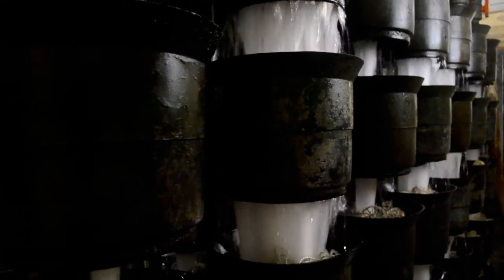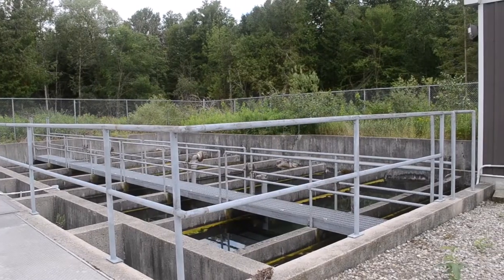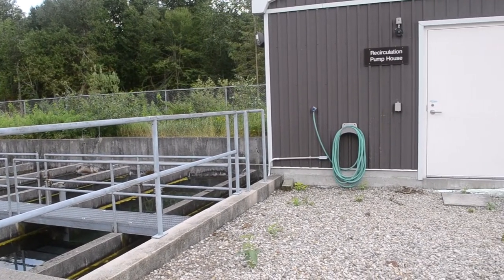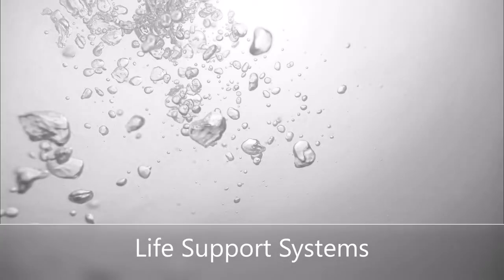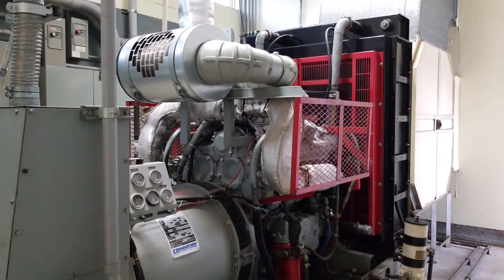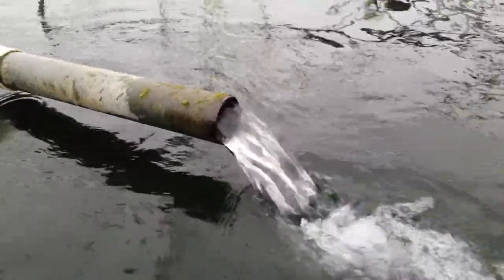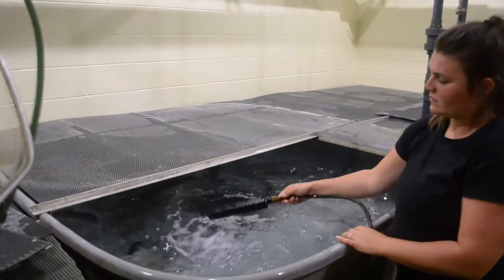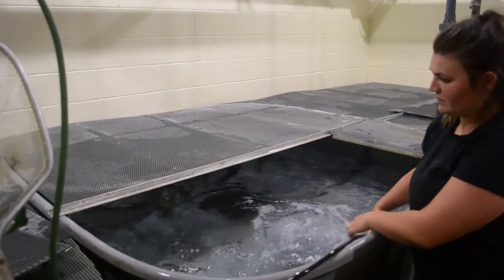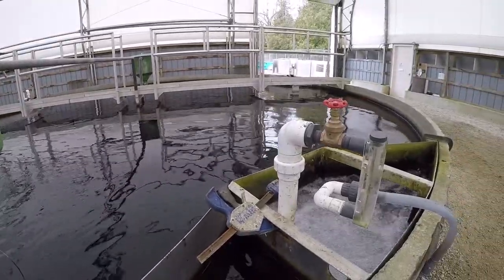The majority of the Research Centre functions as a flow-through system, meaning that water enters the tanks, is retained for a period of time before exiting through the drain, where it eventually ends up in the Wastewater Treatment Centre. Fish require a well-oxygenated environment, which means water always has to be flowing. The station has a backup generator to provide power in case of an emergency. While most water aeration happens in the water tower, individual fish tanks have a small diffuser or air stone, through which air is moved using a blower, providing supplemental oxygen during emergencies when the water supply may be reduced or shut off.